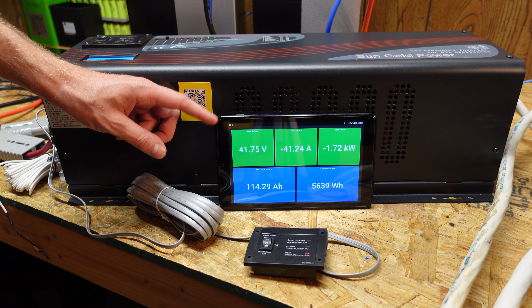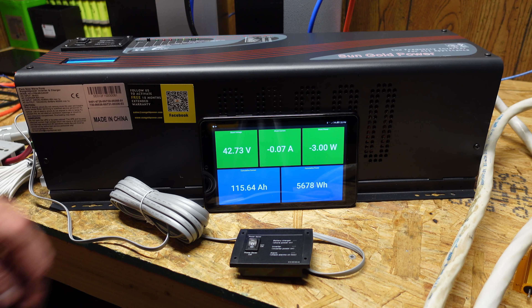And our voltage is dropping quickly, and you can hear the low voltage alarm of the inverter is now sounding. Alright, and there we go. The inverter shut down. Interestingly, the BMS did not trip, so we're just above the trip point of the BMS. And let's wait and see what our final capacity is. And we finished at 115.64 amp hours. These batteries are rated for 120, so that's not bad at all considering that heavy load we had in the beginning.